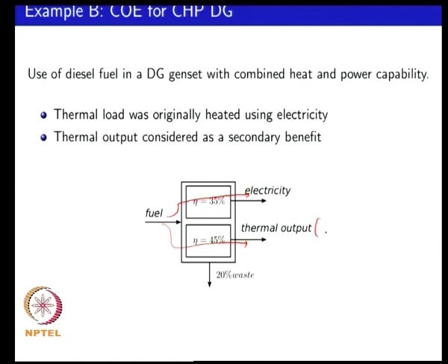So, if you look at now your input energy, it is the same 9.4 kilowatt hours, and your electricity output is 3.3 kilowatt hours per liter, and your thermal output is now 4.3 kilowatt hours.